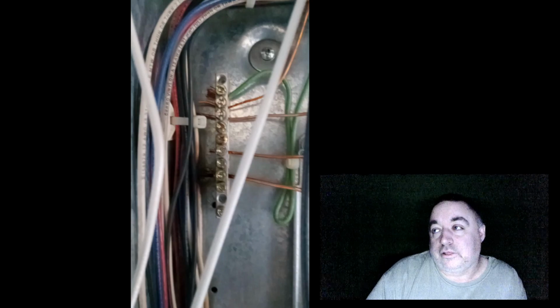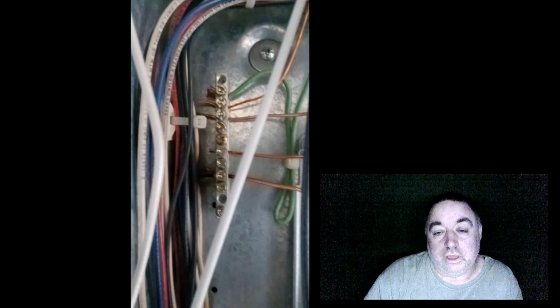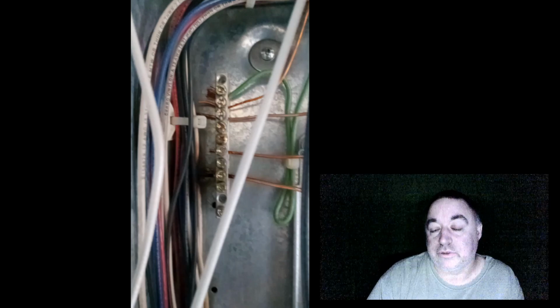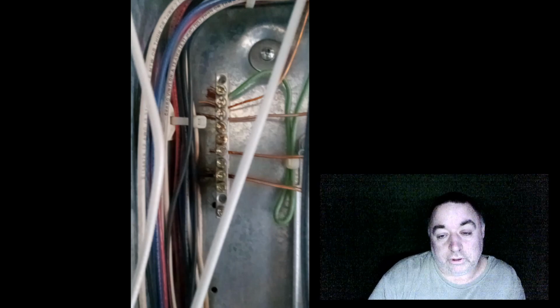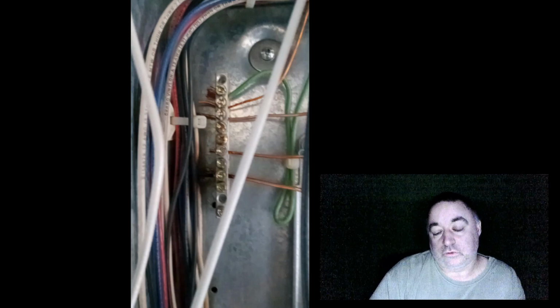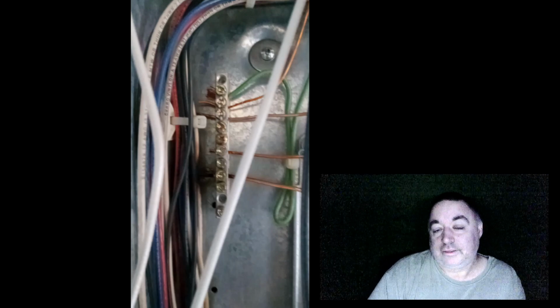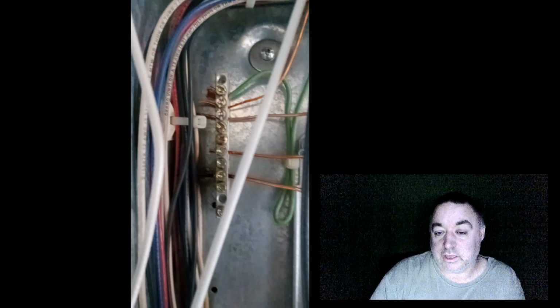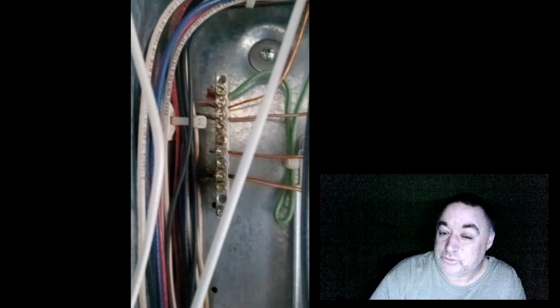The control voltage may be 120 volts at the switches. It is normal for some machine manufacturers, although it's not proper. Codes vary depending on where you're working. I have seen it, though, where a 3-phase control board or 240 volt control board machine that does not call for a neutral but does call for a ground will use the ground as a return path for a very low amperage draw control board, like 500 milliamps or less. Not supposed to do that, but I've seen it happen many times, so I'm guessing that's what's going on with this machine. I don't know.